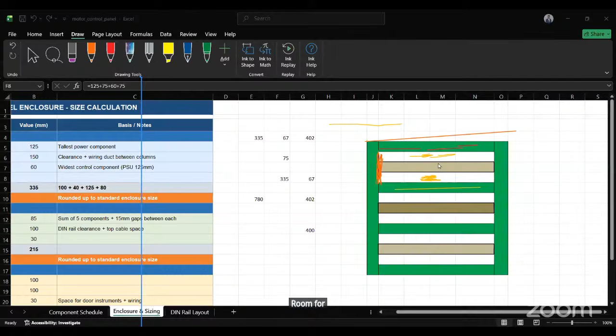Remember that 20% someone was asking about in the comments. That 125, 75, 60, this one, is the total accurate sum we calculated, so we've not left room for buffer or expansion. That's why we now do 20% of the whole calculation, which is 335 times 0.2.